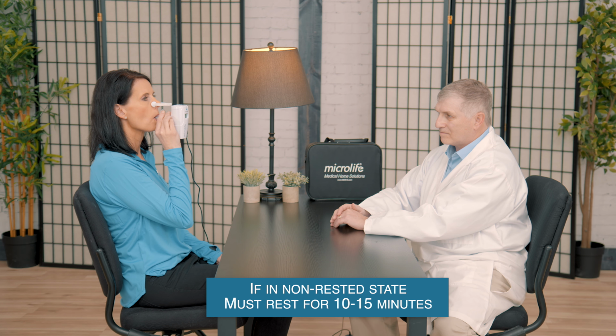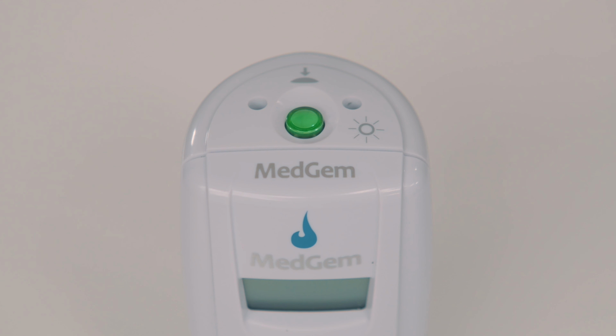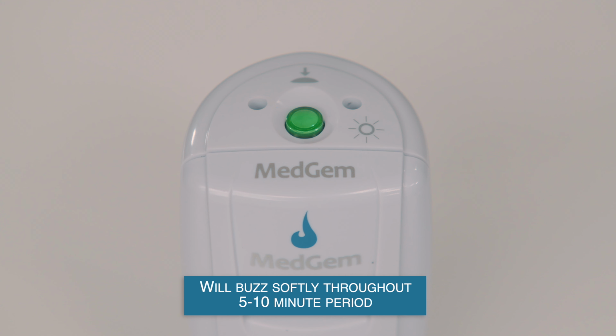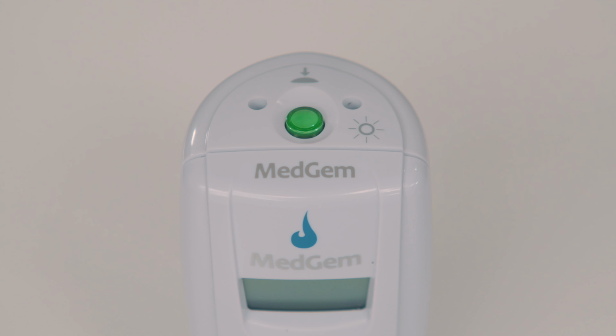Patients who are in a non-rested state should rest for approximately 10 to 15 minutes before the measurement to allow the body to stabilize. To make this as easy as possible, have the patient support their arm on the armrest of the chair, a table, or with the opposite hand. The indicator light will change to a non-flashing green during the measurement, and the MedGem device will buzz softly throughout the 5 to 10 minute measurement period. Measurement time will vary, as the time needed to reach a steady state of breathing is patient-specific.